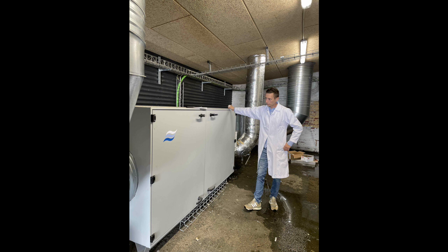Okay, is there anything else that can be done to lower energy consumption? Well, yeah, it's also possible to use a heat exchanger to recover heat energy from the outgoing hot-wet airflow and push it back into the incoming regeneration airflow. Now, this can further reduce the energy consumption of the dehumidifier. Now, whether these energy efficiencies can result in an overall energy cost that is less than the amount of energy being saved by the client is very dependent on the specific project.